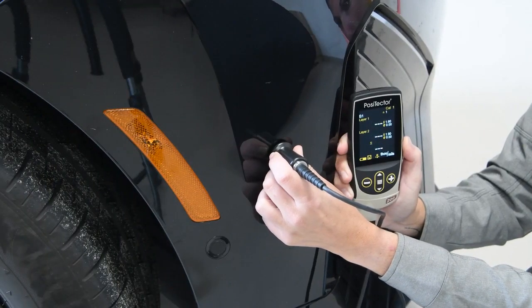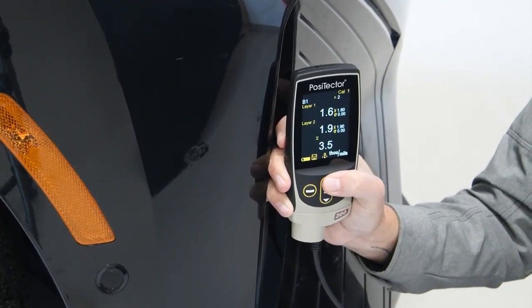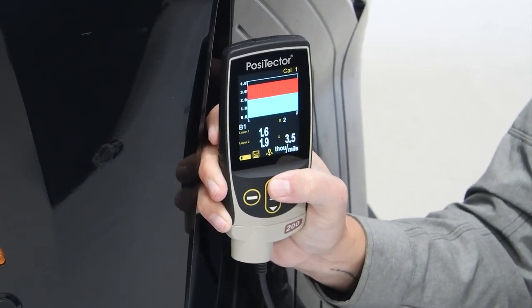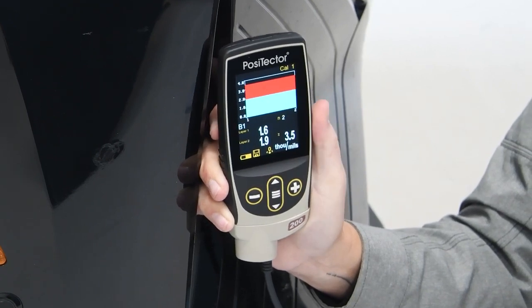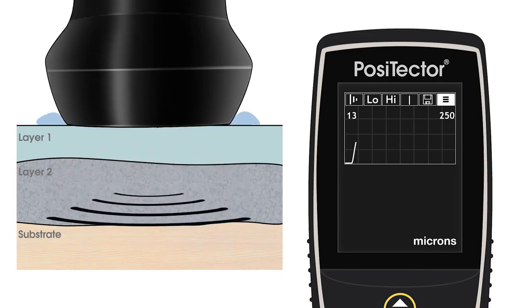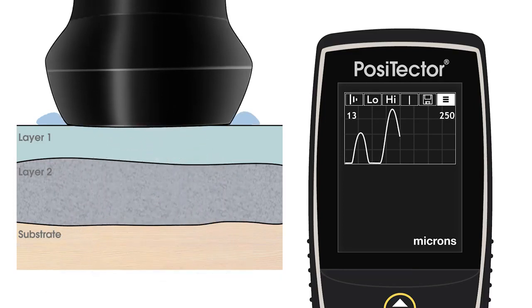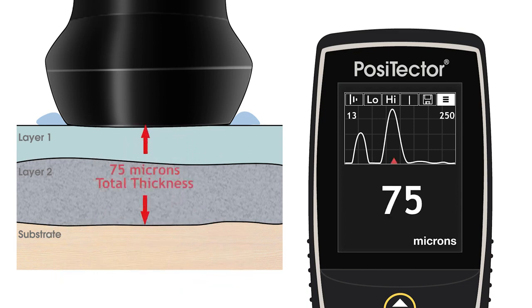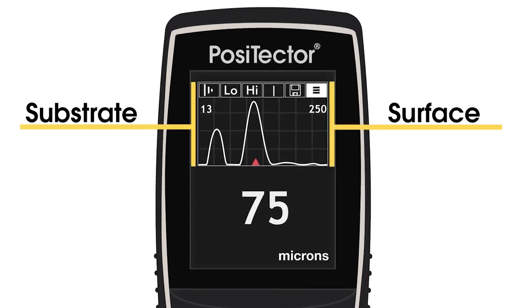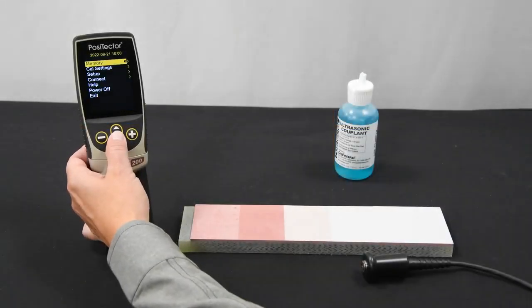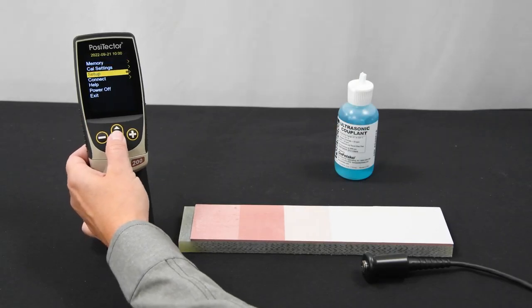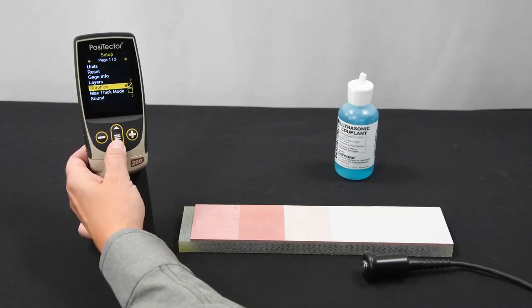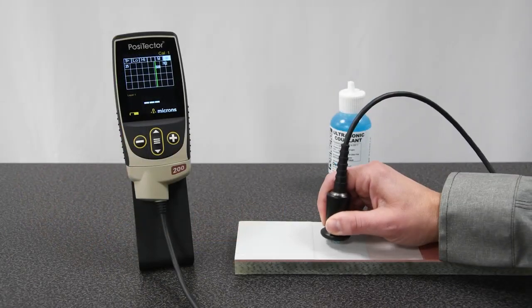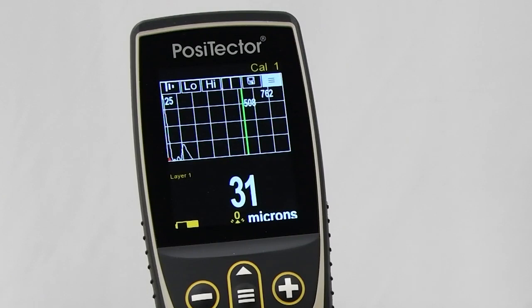When connected to an advanced gauge body, additional features are available. Up to 3 individual coating layers in a multi-layer system can be measured, and graphics mode is available for analyzing the instrument's readings. After each measurement, a graph is displayed showing the reflected ultrasonic pulses. The left and right side of the graph represents the low and high ends of the measurement range, respectively. The strength of each reflection is shown by the height of the peak. Graphics mode is ideal for measuring new or unknown coating systems where the expected coating thickness or number of layers is unknown. A distinct repeatable peak indicates a reliable measurement.